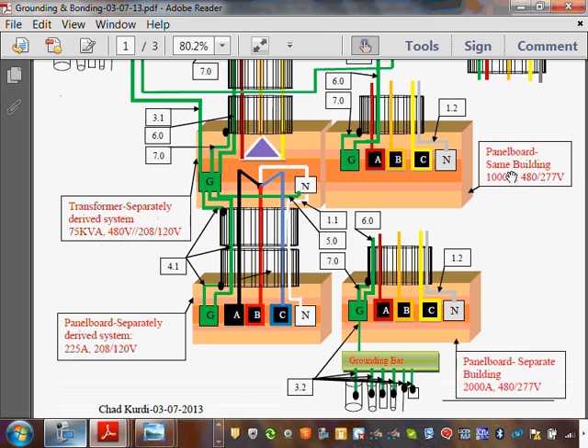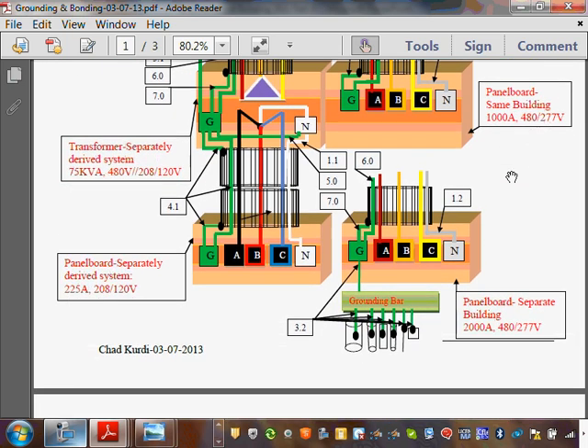Let's go, the one right underneath there. The only difference between the 1000 amp here and the 2000 amp here, other than the amps, is the voltage is still the same. Oh, by the way, with the voltage, if the voltage is 240/120 single phase, would that be different? Absolutely not. So don't let the voltage scare you or the amps scare you. Same. Sizes will be different, of course. But in terms of the naming, in terms of how to size it, it's still the same.